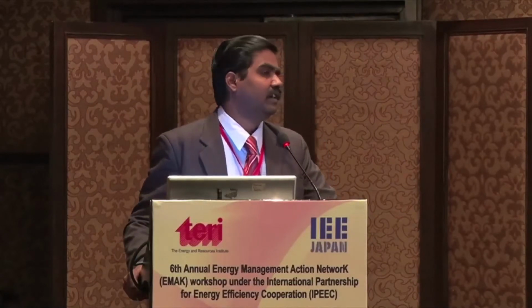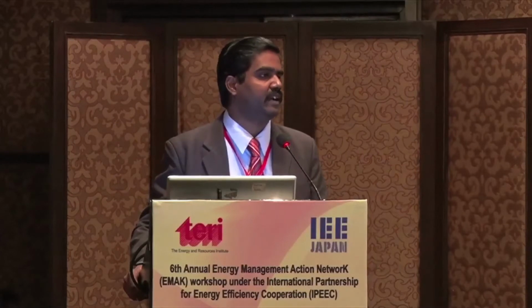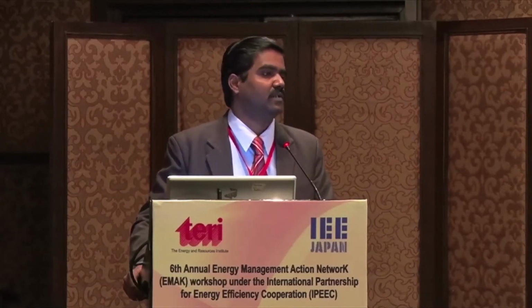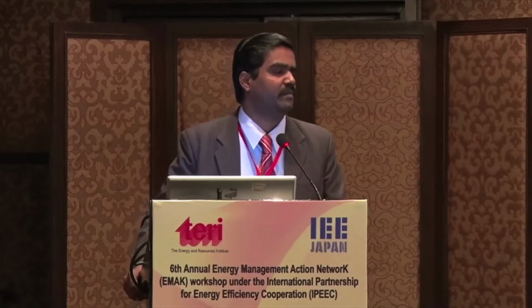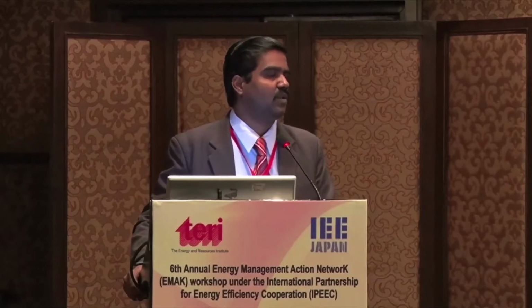This is Tahio Cement, and its capacity is 11,600 ton per day, which is of 2 kilns of 4,000 and 7,600. The total power output is 15 megawatt, and it has been in operation since 1982. And till date, no major maintenance has been done, except only once the superheater tubes were changed. And that's also not because of any maintenance issue, it's because of the change in fuel conditions. So that was the reason we changed the superheater tubes. But apart from that, it's still operating at the rated power of 15 megawatt, and there is no degradation of power for the last 32 years, I can say.